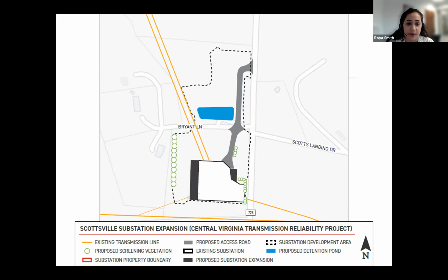The expansion to the west is about 40 feet, to accommodate new distribution equipment including transformers and protection controls. On the eastern side by James River Road, the substation will be expanded in a 45 by 55 foot area to accommodate a new control house building, which will help support the voltage upgrades during construction.